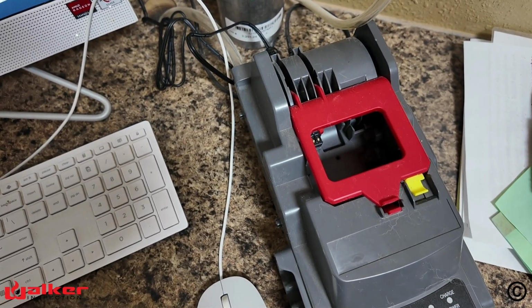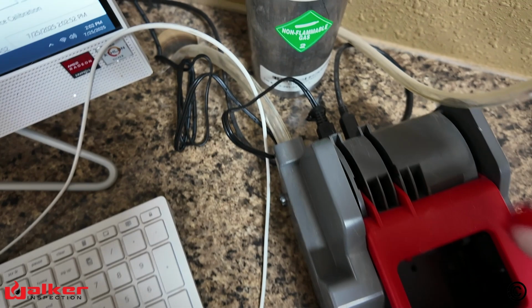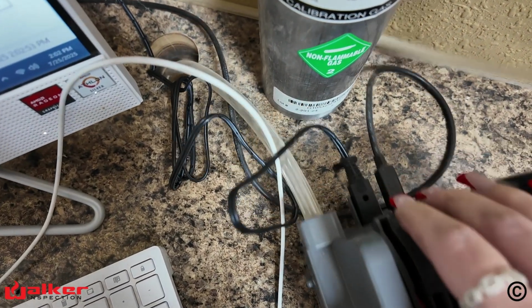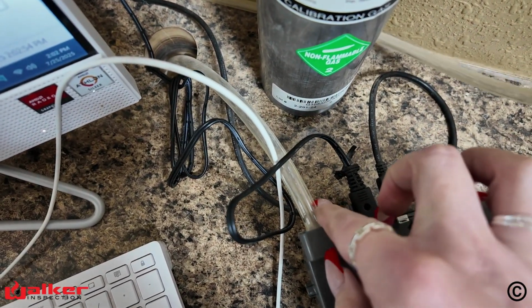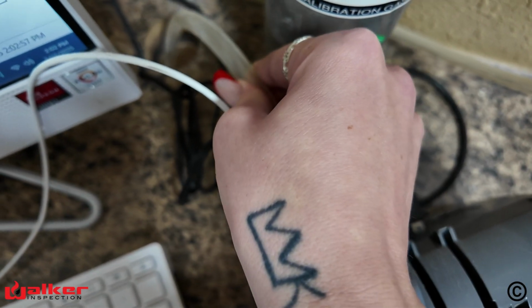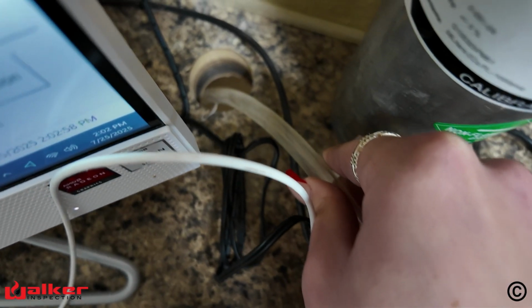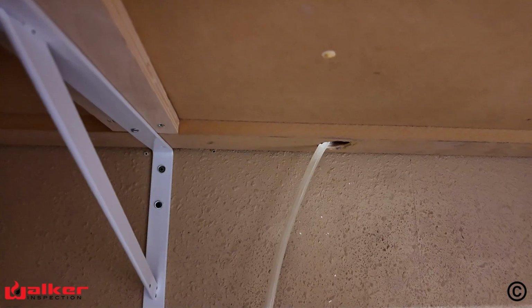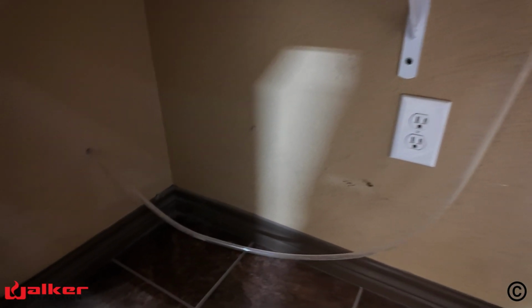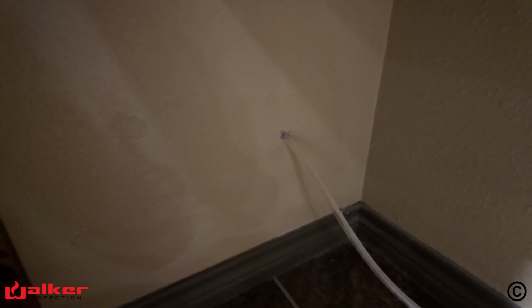The final step is checking that the air hose is fully connected to the back of the docking station. This hose is larger than the gas hose. The other end of this hose will need to run outside for the docking station to get fresh air in order to filter through each one of the gases when calibrating or bump testing the gas monitors. Ensure that this hose is free of any obstructions such as items blocking it, or that it does not have anything pinching the hose off.